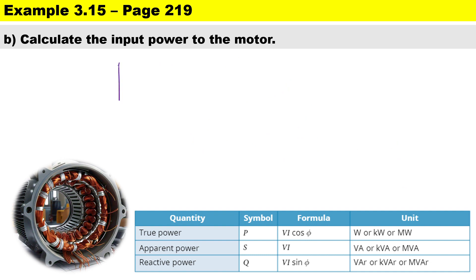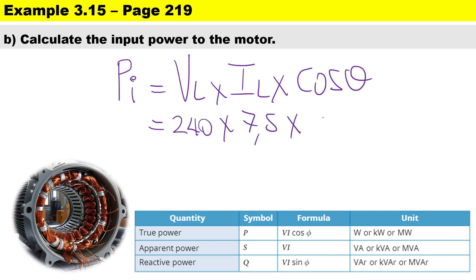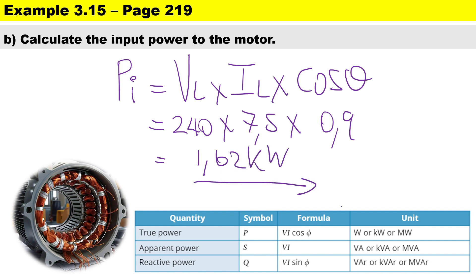To calculate the input power of the motor — remember, for motors we use input power, for generators we use output power — it's the supply voltage multiplied by the supply current times the power factor: 240 volts × 7.5 × 0.9 = 1.62 kilowatts. That is the actual power consumed in the circuit.